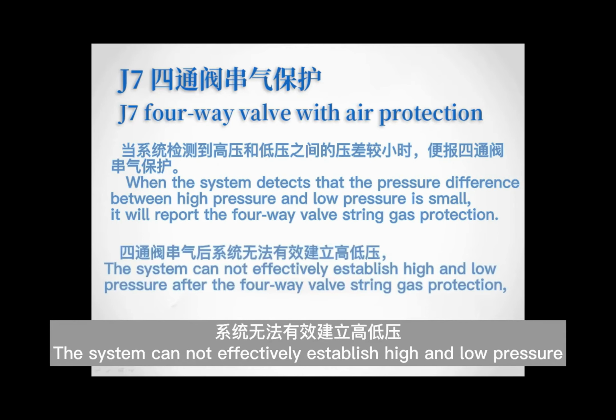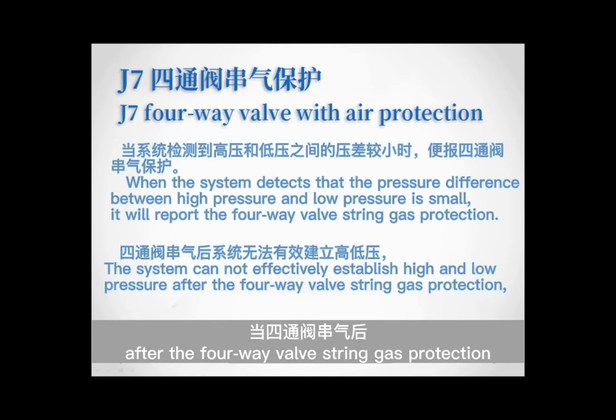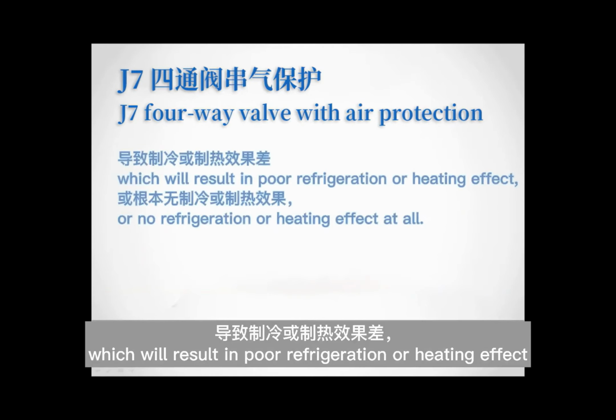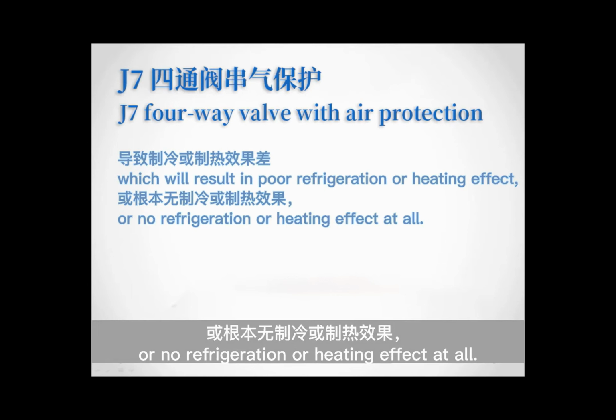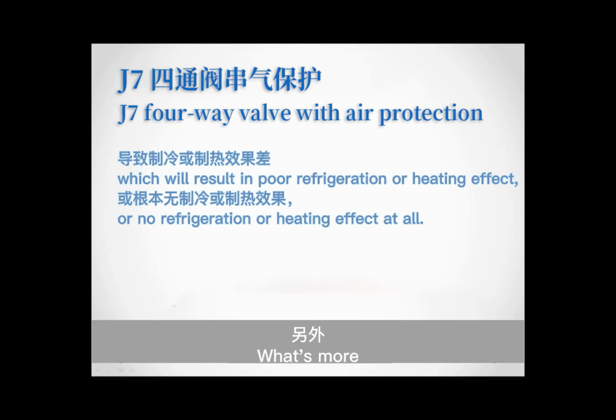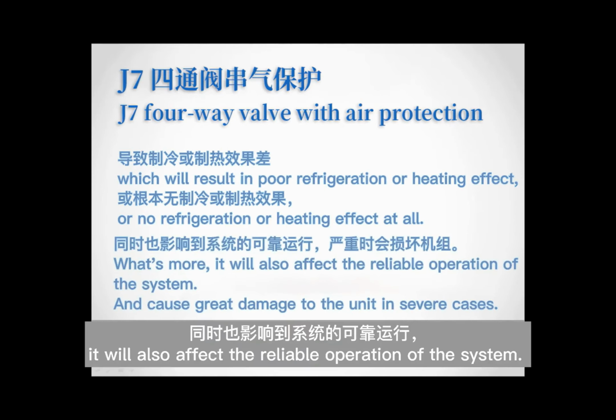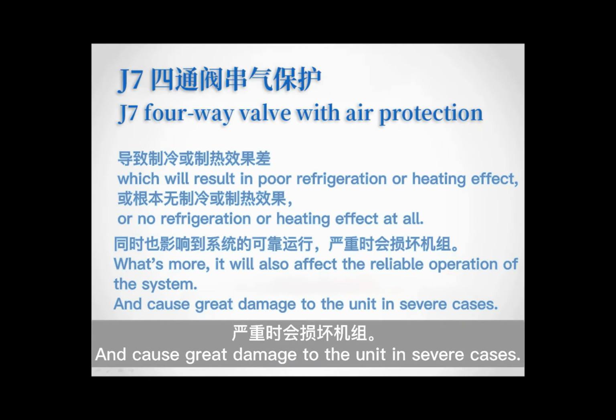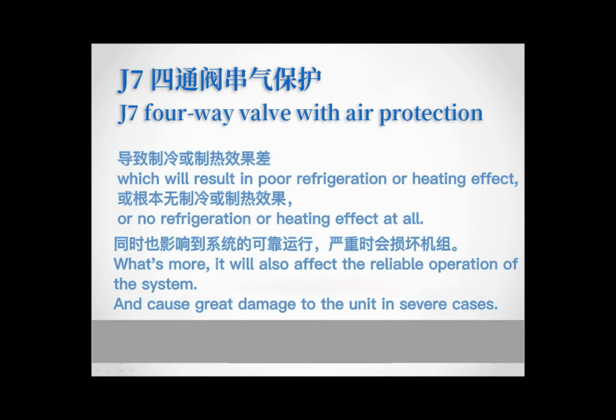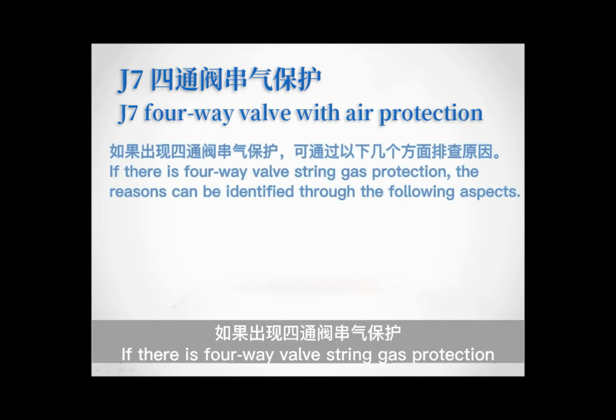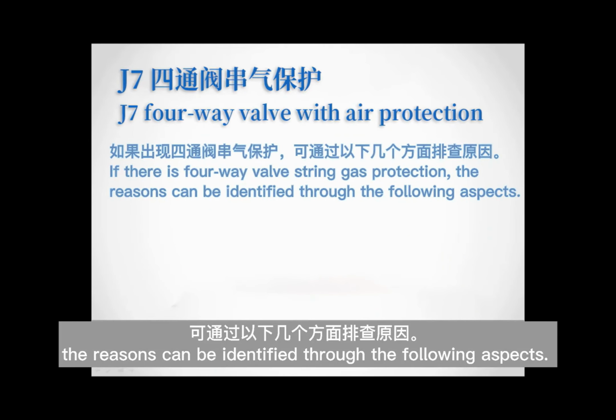The system cannot effectively establish high and low pressure after the four-way valve string gas protection, which will result in poor refrigeration or heating effect, or no refrigeration or heating effect at all. What's more, it will also affect the reliable operation of the system, and cause great damage to the unit in severe cases. If there is four-way valve string gas protection, the reasons can be identified through the following aspects.